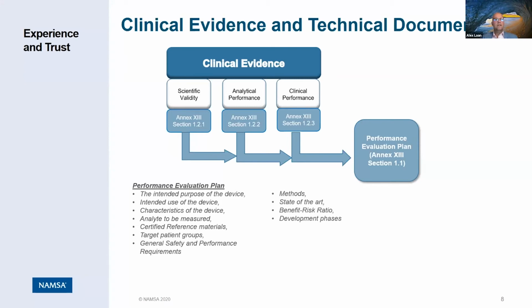Another interesting aspect is the benefit-risk ratio. This is perhaps a new element in the IVD regulation. I think in the United States, we're more used to defining that. The benefit-risk analysis and the benefit-risk ratio is a must-have. The ISO 14971 standard may give you a possibility not to do it when it is clear that the residual risks are below a particular threshold value. However, the IVDR, since it is law, basically does not give any criteria for not doing it. So you need to do it.